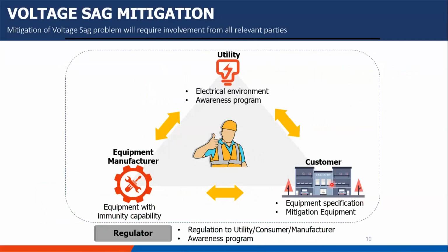Okay, so voltage sag mitigation is not solo. It doesn't depend on one party only. It depends on the four. The utility itself needs to play a role by having a good electrical environment to reduce the fault occurrences and reduce the fault severity, and the utility needs to run awareness programs to make the customers understand.